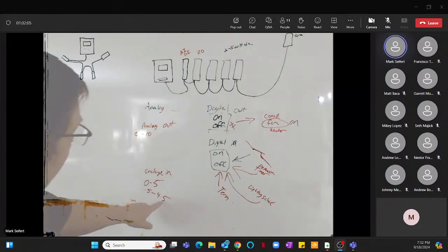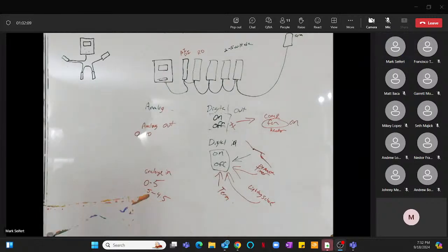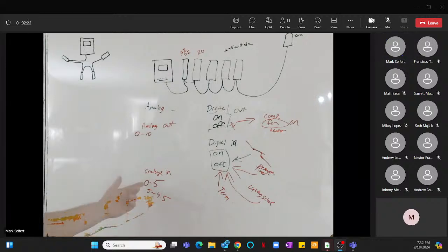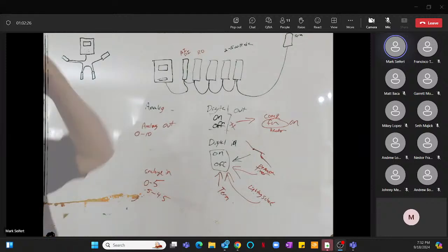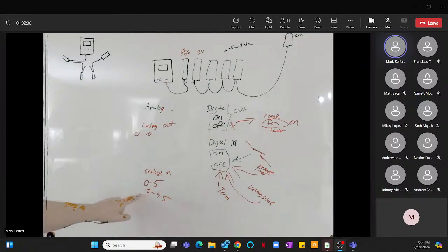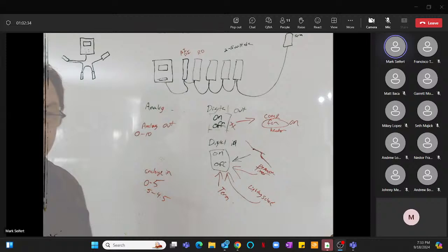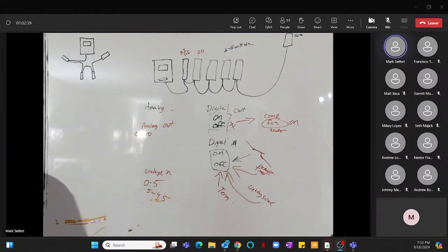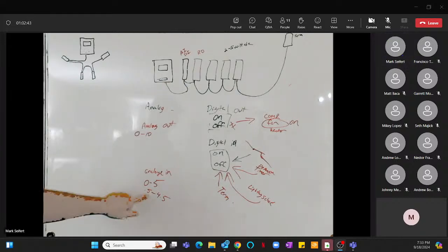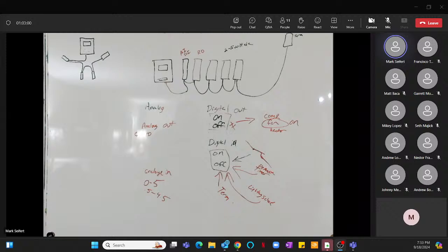The reason it's 0.5 to 4.5 is so that you can tell if it's failed. If you had 0 to 5 and somebody unplugged it, you would just have 0 volts, it would just say 0, and you wouldn't be able to know. If it failed and had 0 volts, you would never know. The only reason you can see these things have failed is because it's 0.5 to 4.5. If it sees a 0, it knows it's failed. That's the only reason. The 4.5 is kind of the same thing, I guess, but it's mainly for the 0.5. It has to know if it's failed, if it's unplugged, if it's lost its power supply, if it's failed. That's how it knows. So when you see these shorted sensors or whatnot, that's why it knows. That's the reason.